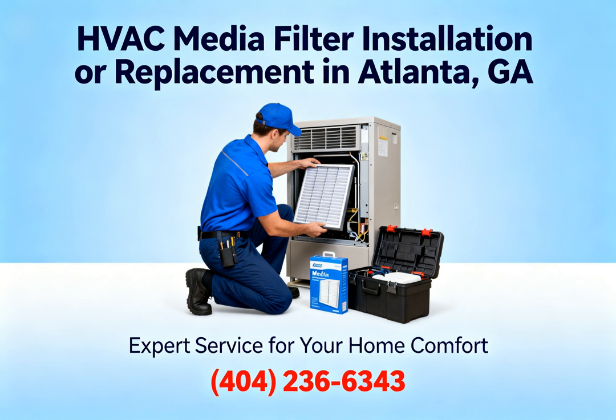This is why the third step, the seal and calibrate process, is non-negotiable. Professionals use specialized mastic sealant or heavy-duty HVAC foil tape to ensure the cabinet is 100% airtight. So the air has no choice. Right. The air must be forced, with no alternative escape routes, to travel through the 40 square feet of deep-pleated media. The blower motor, the ductwork geometry, and the airtight seal must operate in absolute harmony to successfully clean the air without freezing the coils.